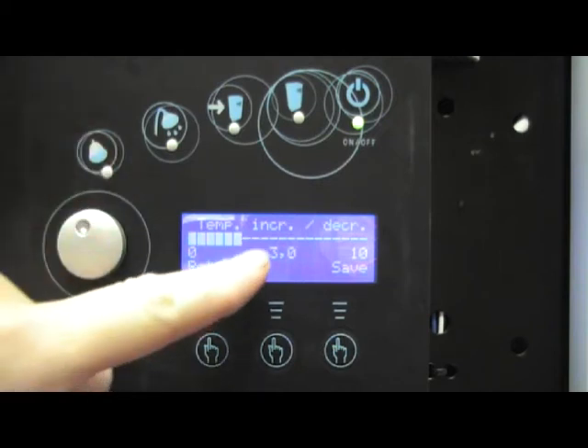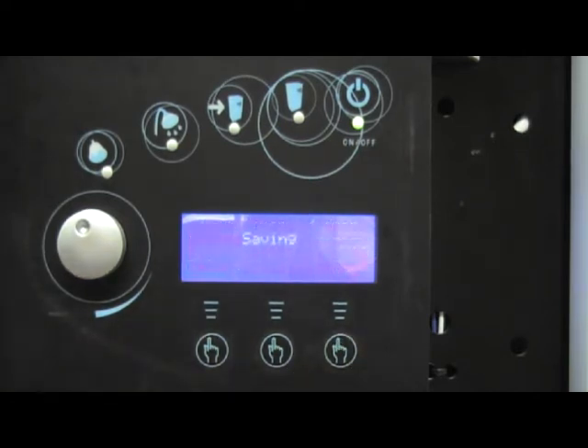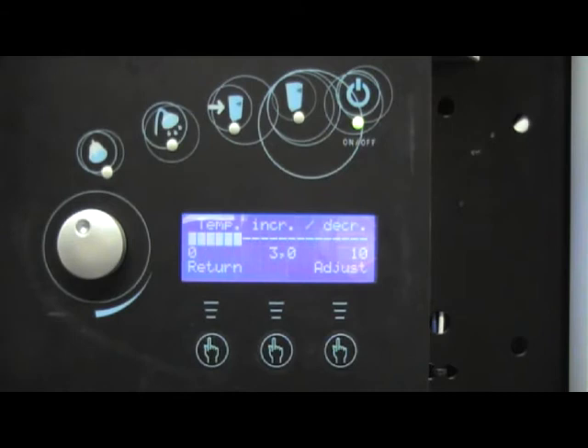Once we are happy now that it is at 3, we press the save. The heat pump will automatically calculate the temperature to send to the underfloor system based on the outdoor temperature.